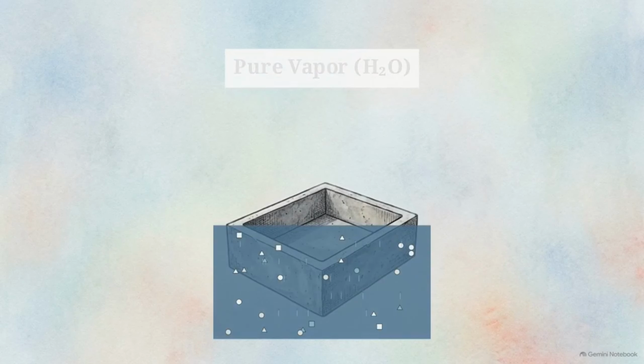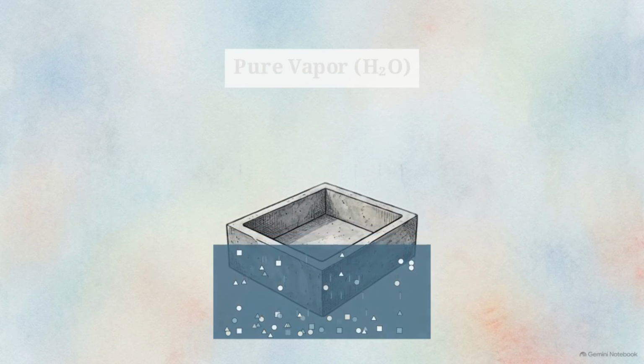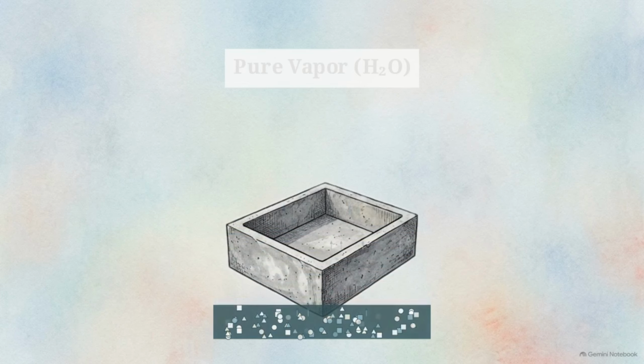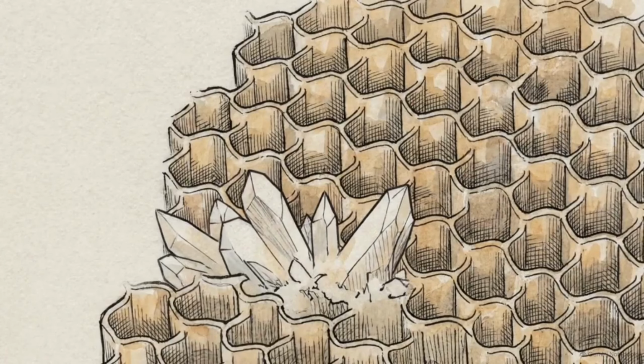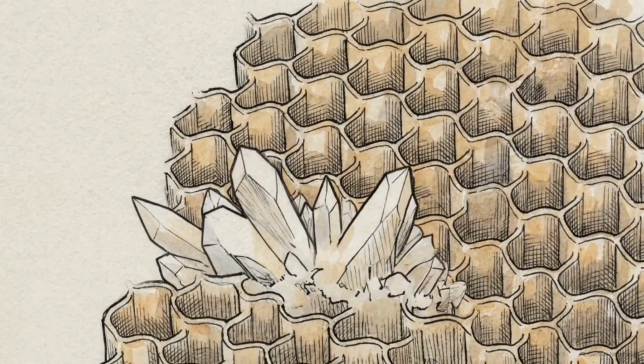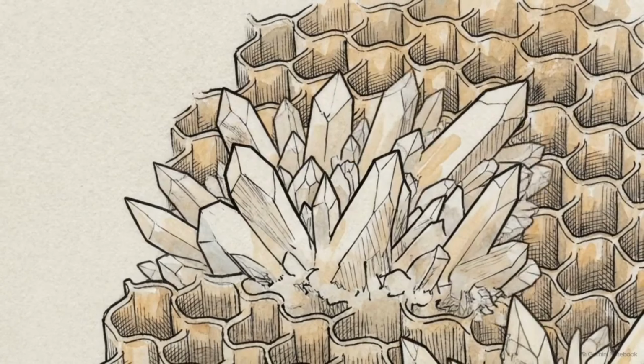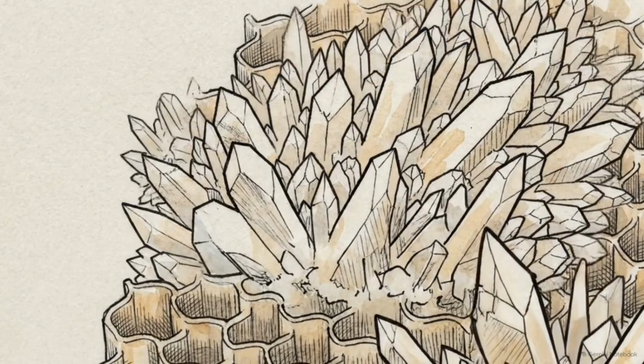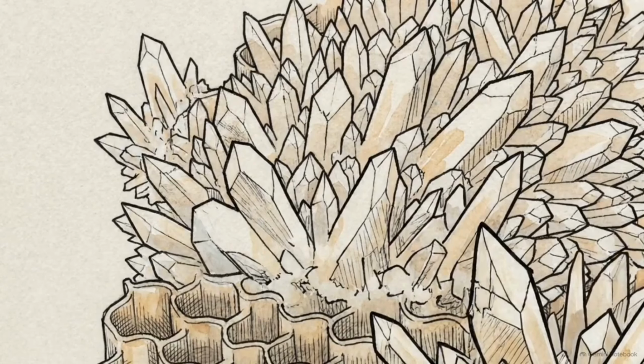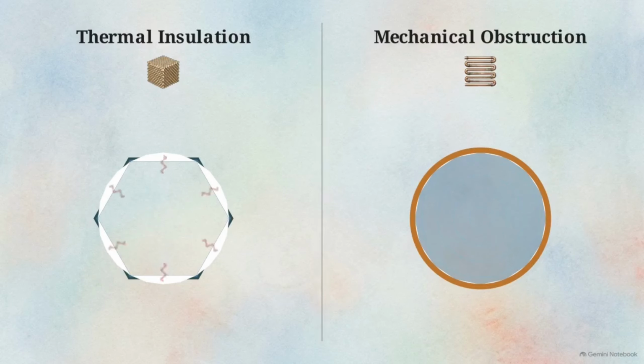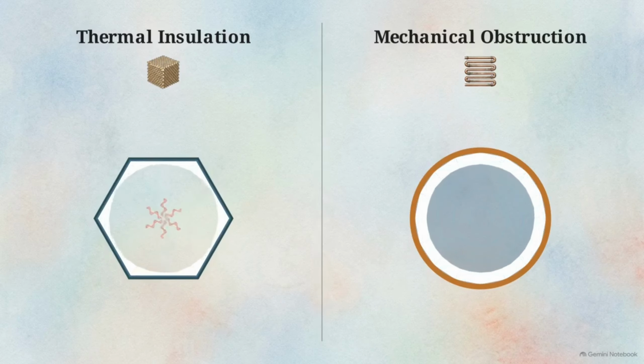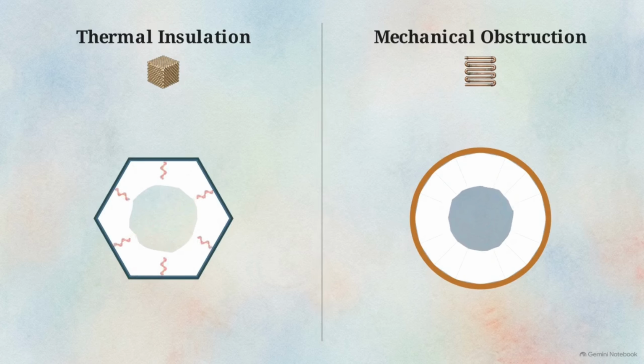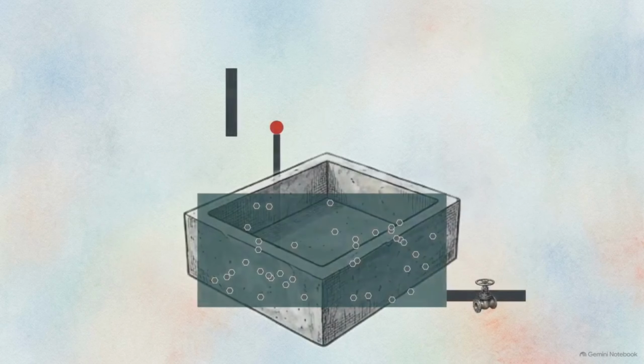When water evaporates, it leaves as pure vapor. This strands all its dissolved minerals, salts, and suspended solids behind in the basin. If left unchecked, these concentrated minerals trigger catastrophic scaling. Calcium and magnesium crystallize, rapidly encrusting the internal surfaces of the system. This mineral scale acts as a stubborn insulator, destroying the heat transfer efficiency of the fill media and eventually choking the chiller's condenser tubes. The automated mechanical solution is the blowdown system.